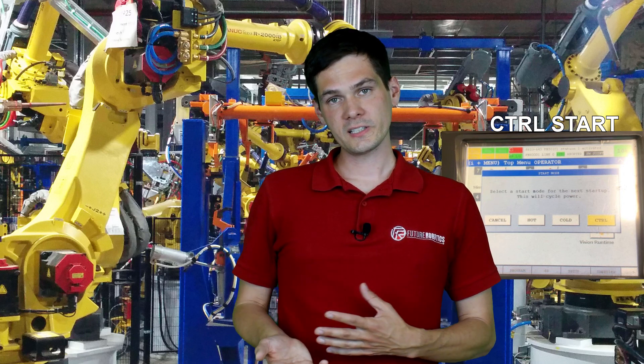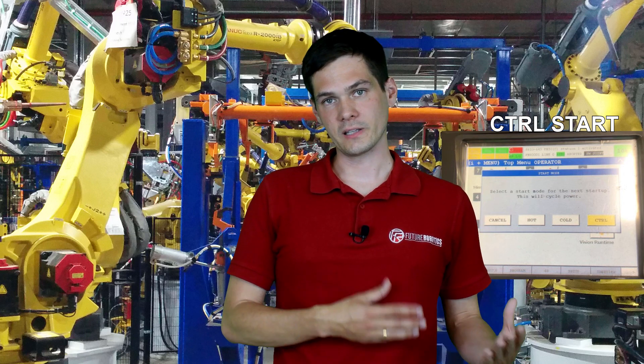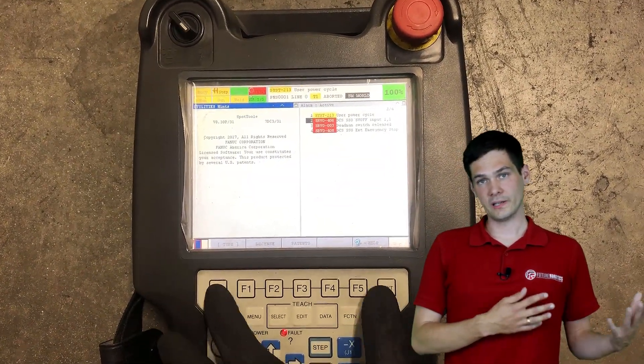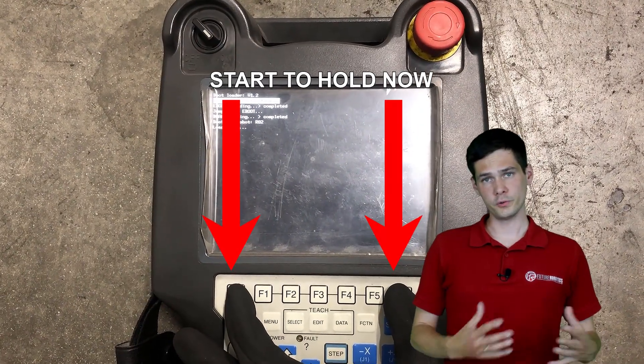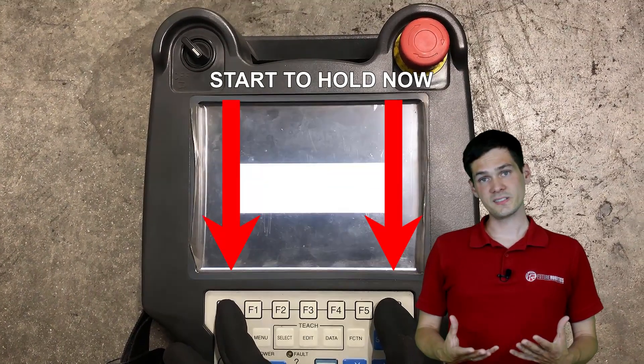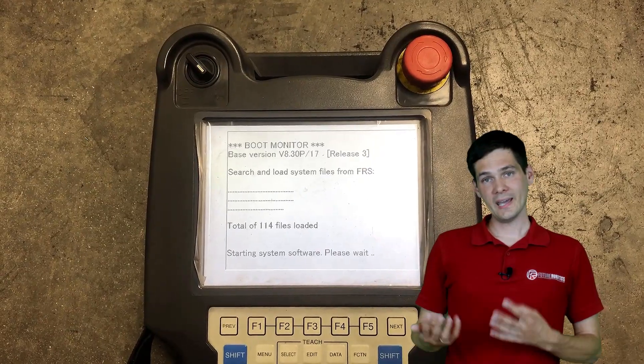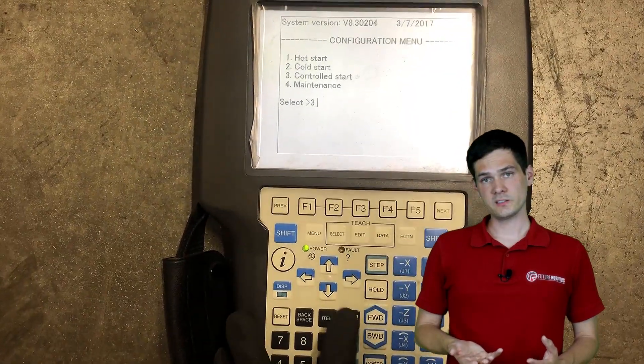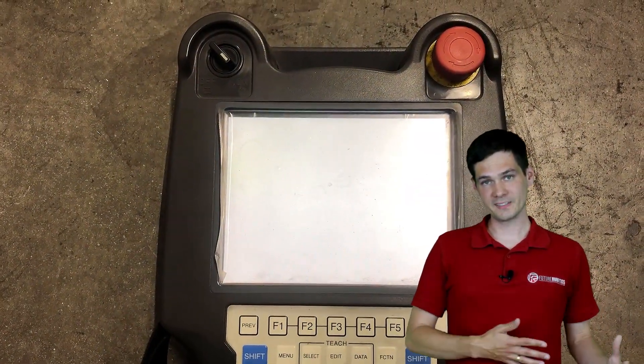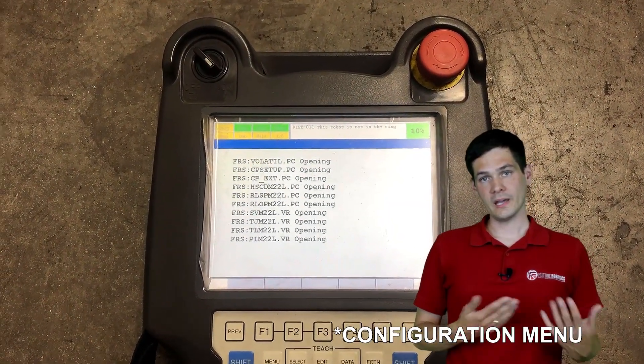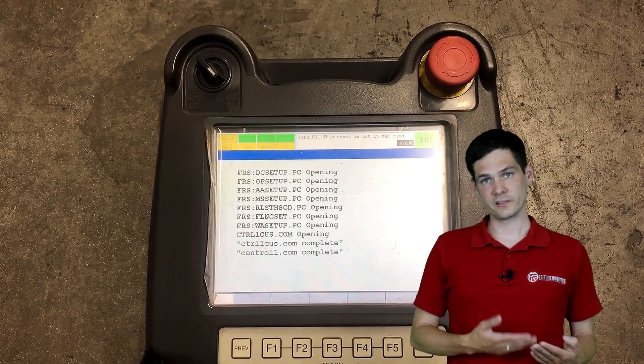The next type of cycle power we have is a controlled start. Controlled start allows you to enter additional options that are not available while the robot is running. It may unlock some variables that you can change that cannot be changed under a regular start, and it allows you to restore the controller backup and do a few other things. You can access this by going through the function menu and simply selecting control start, and the robot will automatically boot to the control start. The other way is by holding the PREV and NEXT buttons while cycling power the controller, which will take you to the boot option menu where you can select the controlled start.